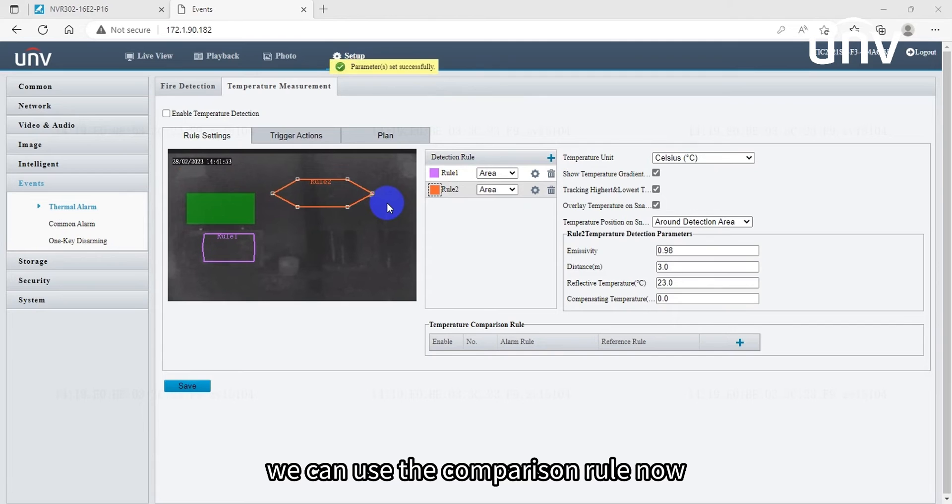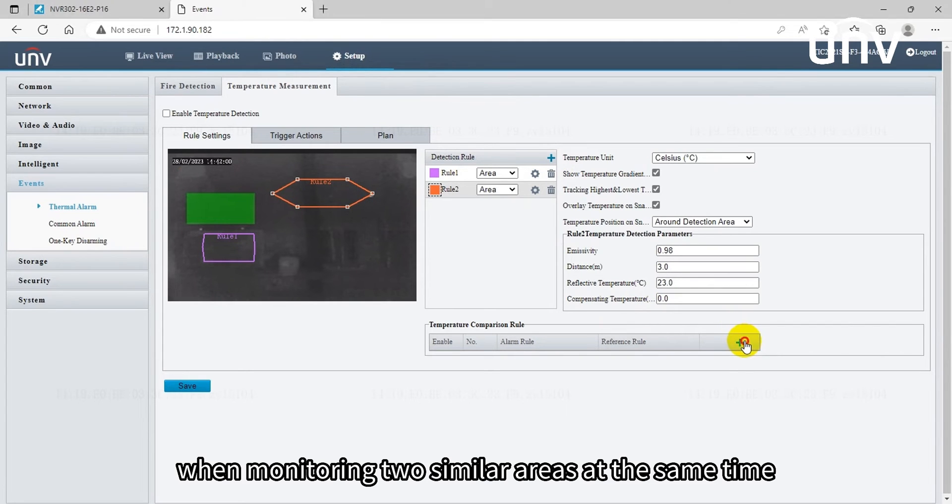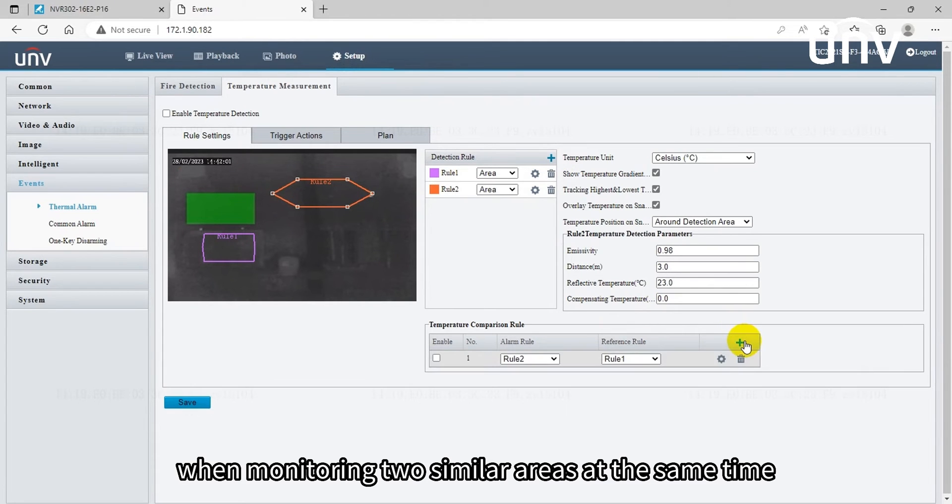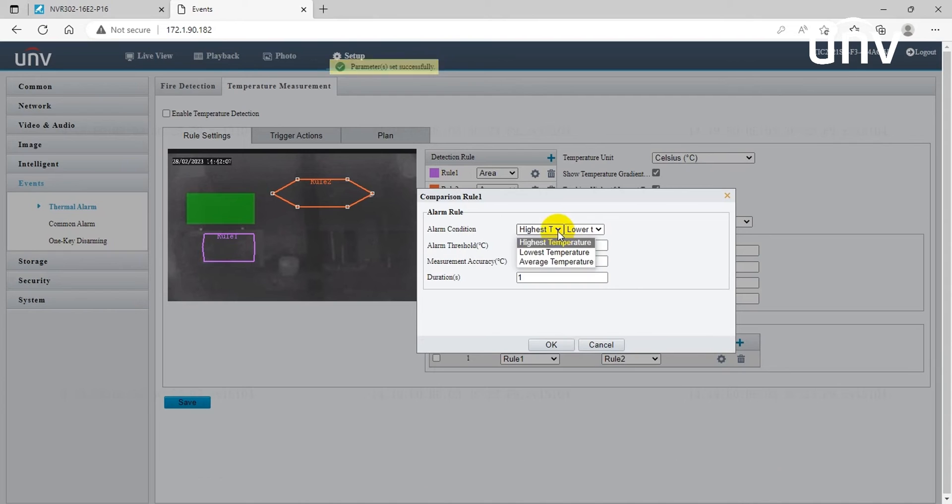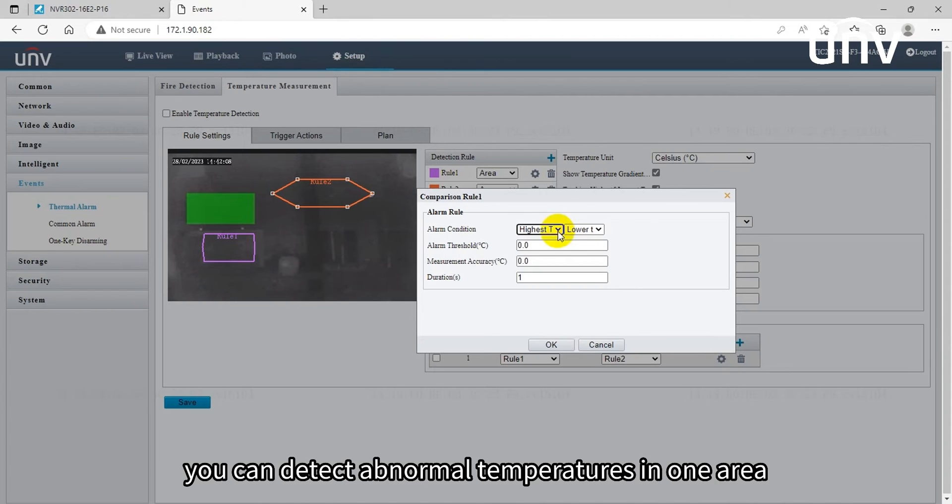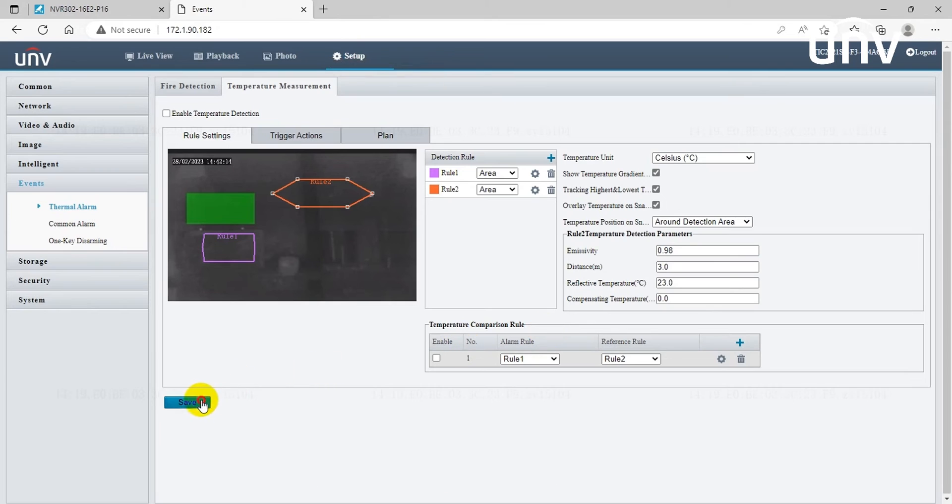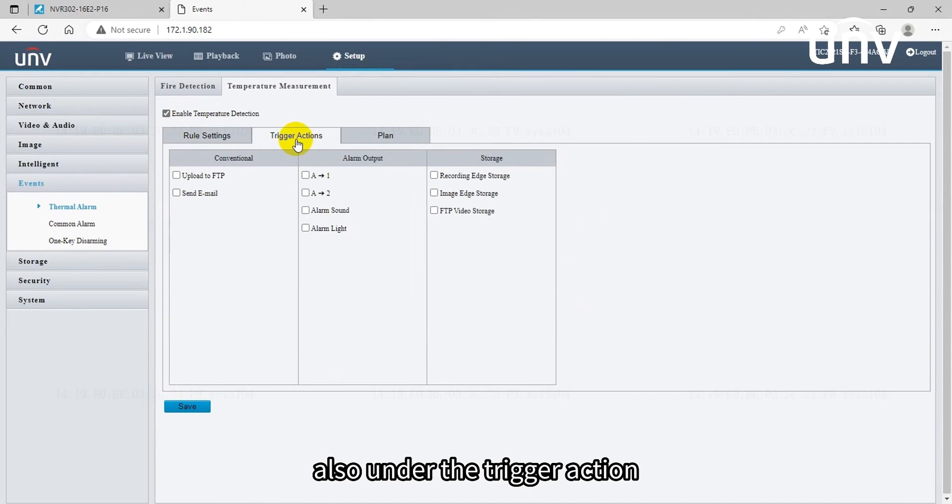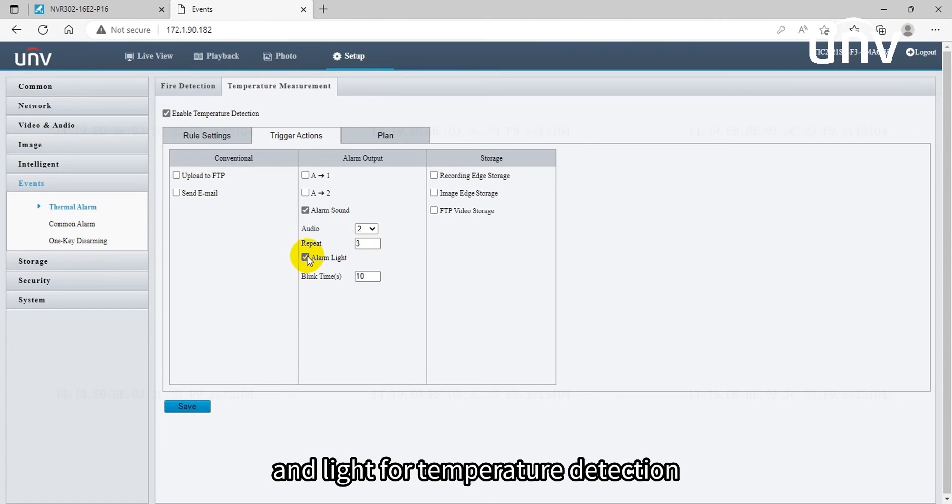After setting up two rules we can use the comparison rule. When monitoring two similar areas at the same time, you can detect abnormal temperatures in one area by comparing the temperatures. Also under the trigger action we can set up the trigger alarm sound and light for temperature detection.